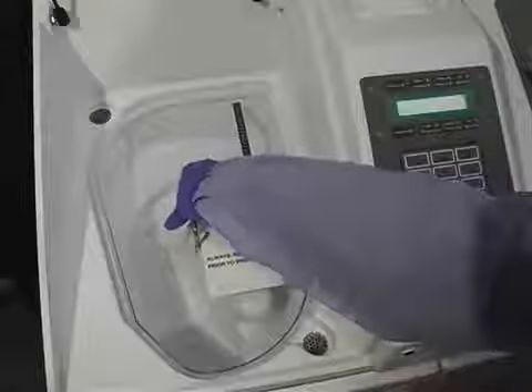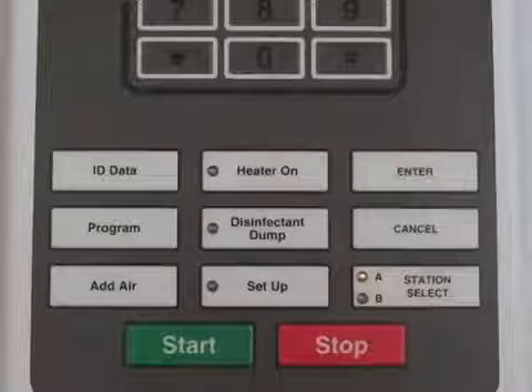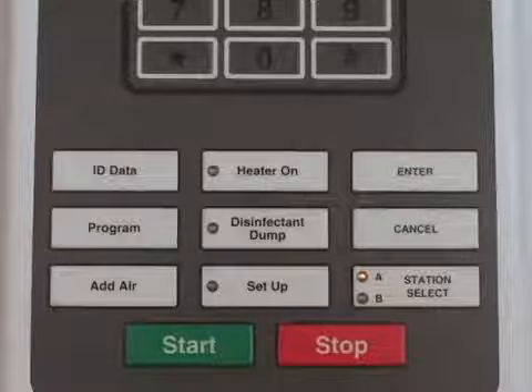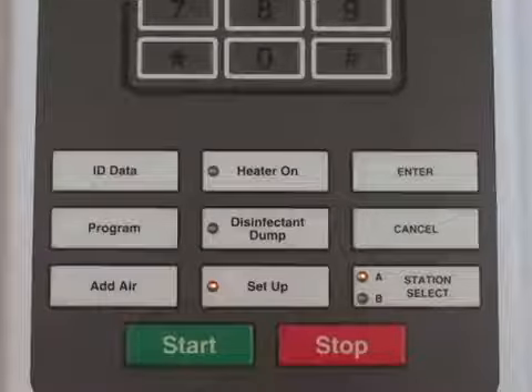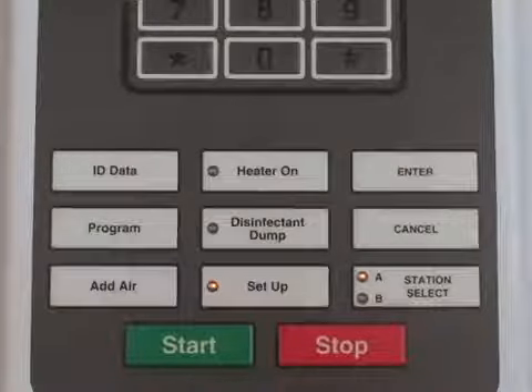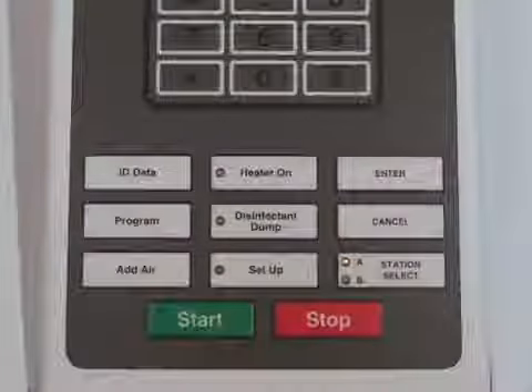The rest of the process is automatically performed by the software by using Setup Function 6. To activate Setup Function 6, press Setup, press 6, Enter, press Start. The DSD will prompt you to attach restrictors. Ensure basin restrictors are in both the A and B basins. Then press Start again.